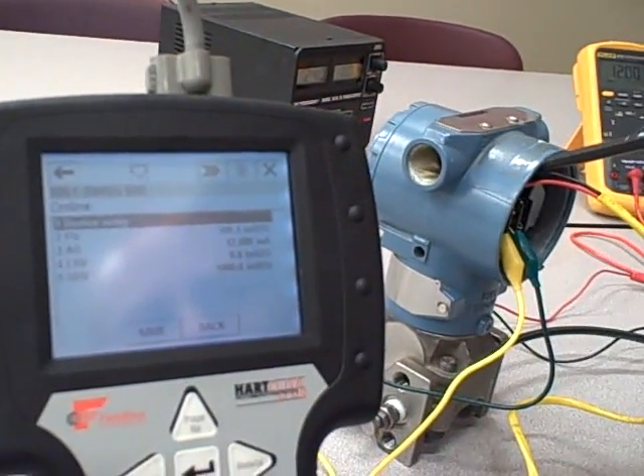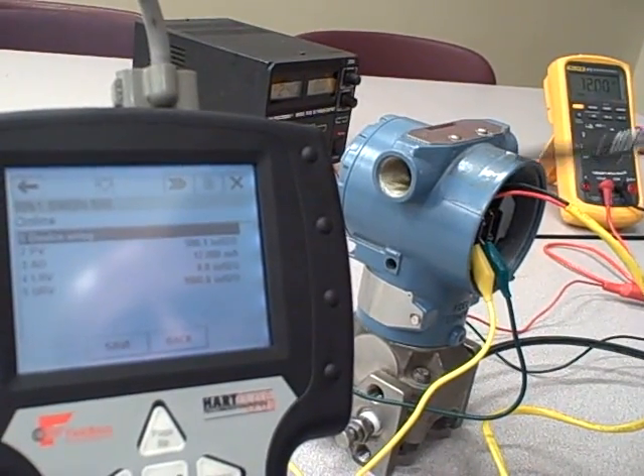What we're looking at here is the screen of an Emerson Model 375 HART communicator as it's communicating with a Rosemount Model 3051 differential pressure transmitter. To this transmitter we have applied about 500 inches of water column air pressure to the high side.